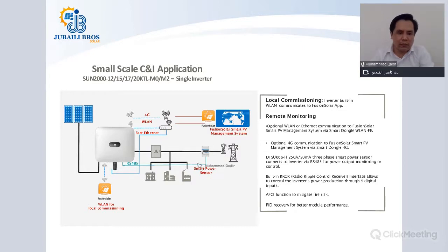In this scenario, if you want to do local commissioning, you will be using the FusionSolar app, and you will be using the built-in Wi-Fi of this inverter. When you are close to this inverter, if you turn on your mobile Wi-Fi, you will see the internal Wi-Fi of this inverter, to which you can connect, and the initial password is normally Changeme. For remote monitoring, you have optional WLAN or Ethernet communication to the FusionSolar Smart PV management system, and the device can be a WLAN-FE dongle or a 4G dongle.